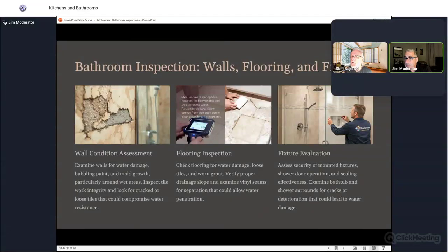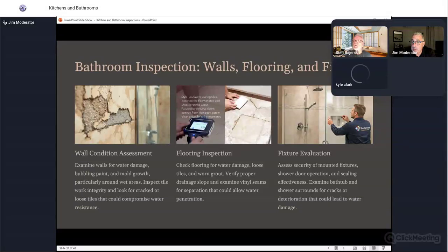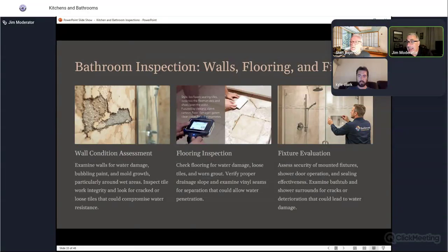Yes, so that's a good question, Giuseppe. So we have a question here. It's very common to test the GFCI in older bathrooms that are not grounded. The button on the tester will not trip, but the test button does. Do you fault it? So we come into that more and more.